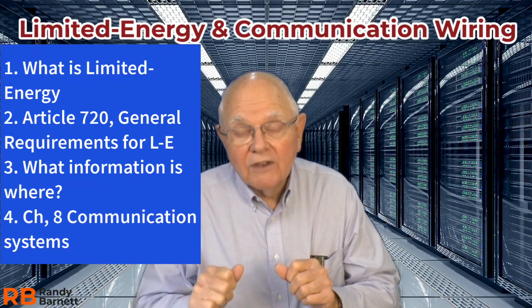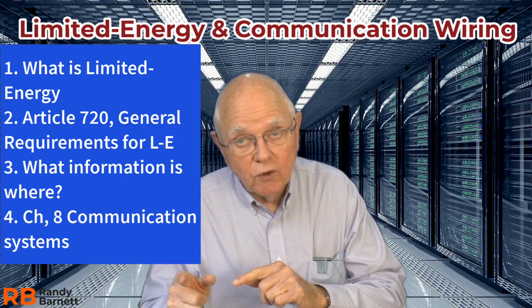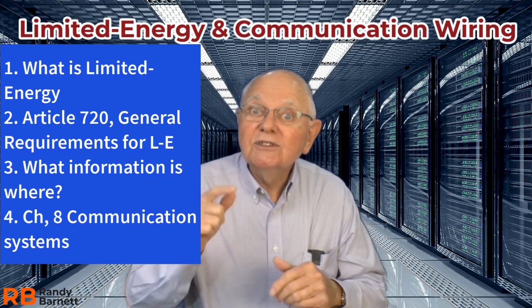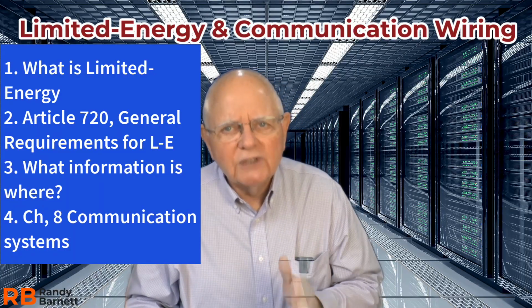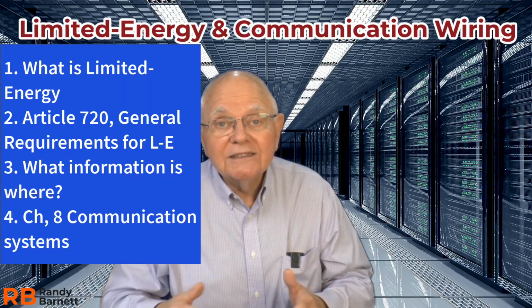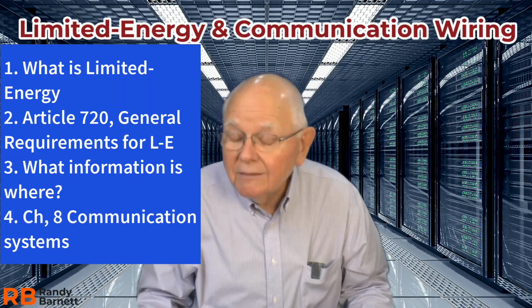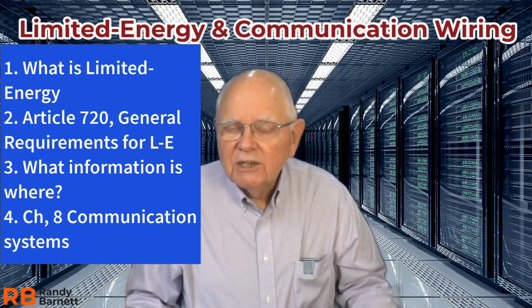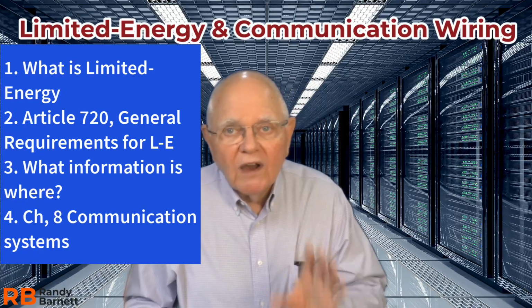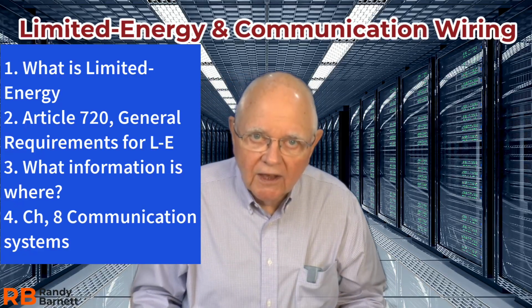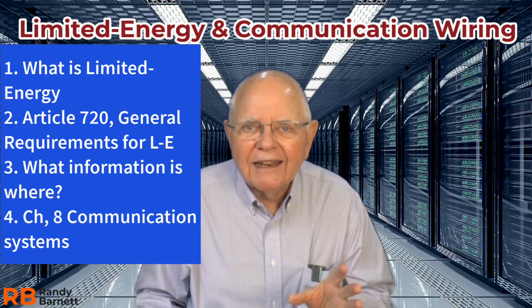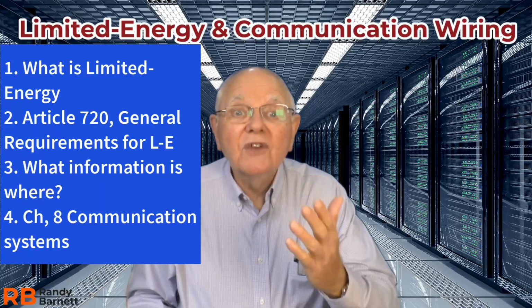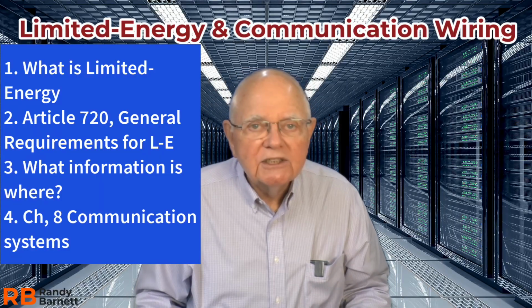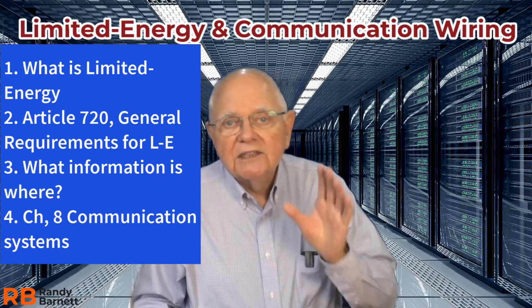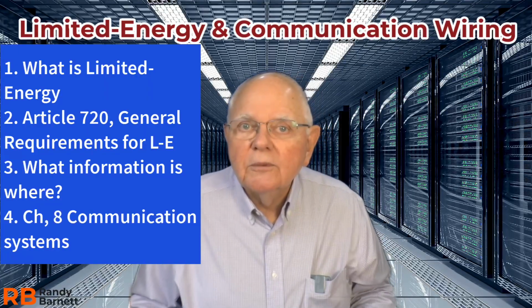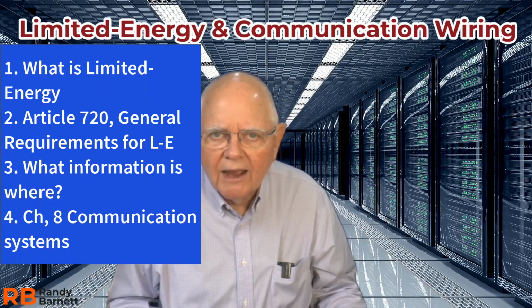Now, we're going to first look at this definition, and then we're going to move into Article 720. Article 720 is a new article, but it covers the general requirements for limited energy systems. So we'll go somewhat in depth into that. Then the next thing we're going to do is take a look at several new articles for limited energy systems, and see what kind of information is in those articles, where we would go to find that information and even to find the article itself. Then we'll take a quick look at Chapter 8, which is communication systems. However, even the title for Chapter 8 in the 2026 NEC changed. It's no longer just communication systems. It's now communication systems for, outside and entering the building. So that's a little bit different. And so we'll talk about that as we wrap up the day.